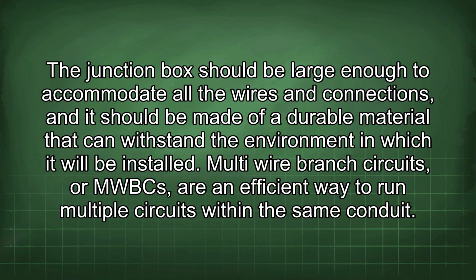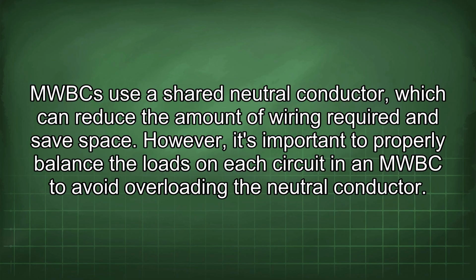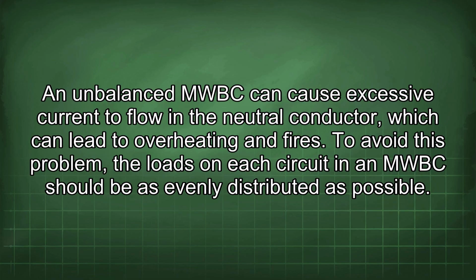Multi-wire branch circuits, or MWBCs, are an efficient way to run multiple circuits within the same conduit. MWBCs use a shared neutral conductor, which can reduce the amount of wiring required and save space. However, it's important to properly balance the loads on each circuit in an MWBC to avoid overloading the neutral conductor. An unbalanced MWBC can cause excessive current to flow in the neutral conductor, which can lead to overheating and fires. To avoid this problem, the loads on each circuit in an MWBC should be as evenly distributed as possible.